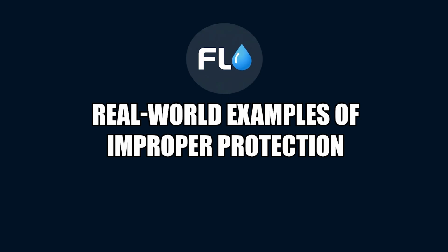What are some examples of places where you've been in the field and you've seen that the level of protection doesn't match the hazard level? Well, we see it a lot when we conduct the CSIs. I've seen large complexes where the irrigator didn't know. They put in a double check, and they had an on-site sewer system.